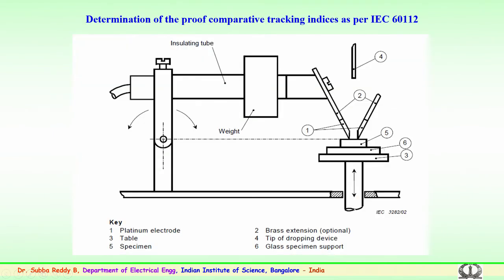The first one is the determination of the proof and comparative tracking index. This test is as per the IEC 60112 standard. Basically, you have an experimental arrangement which is fabricated.